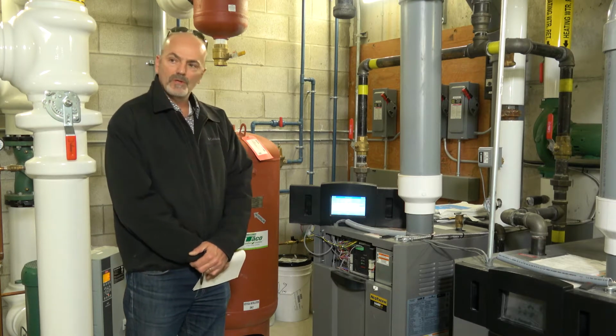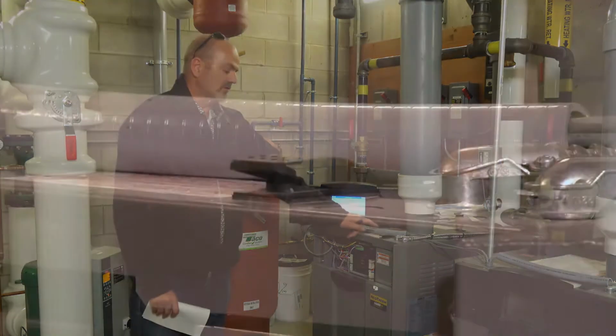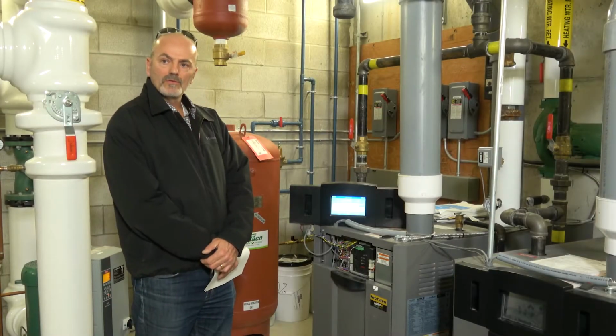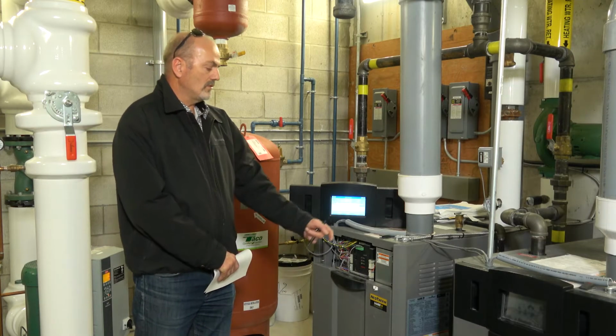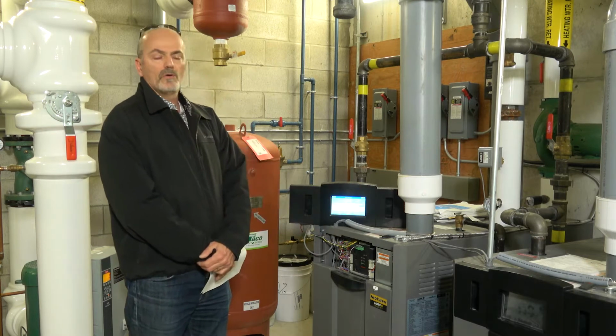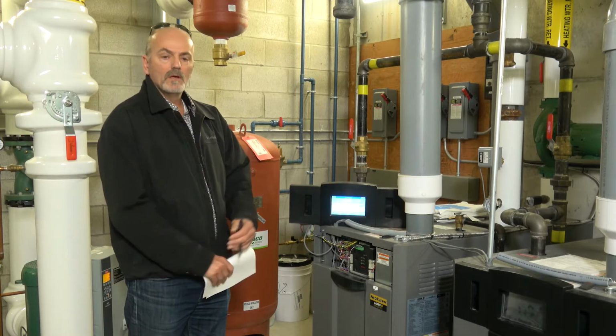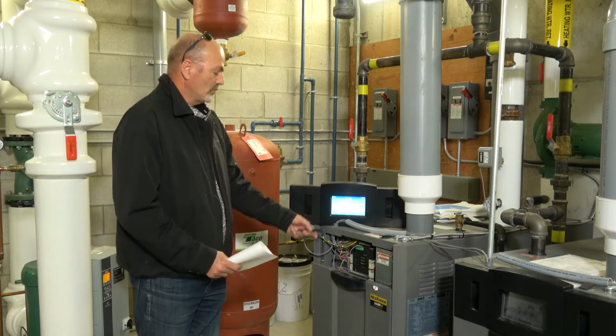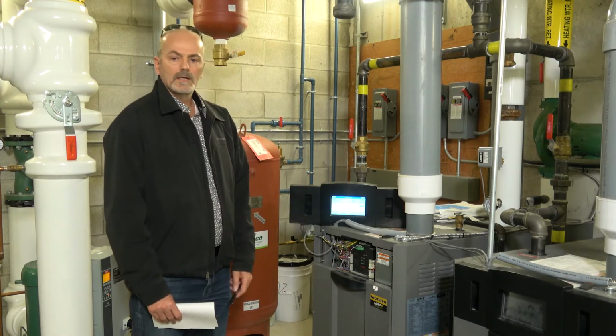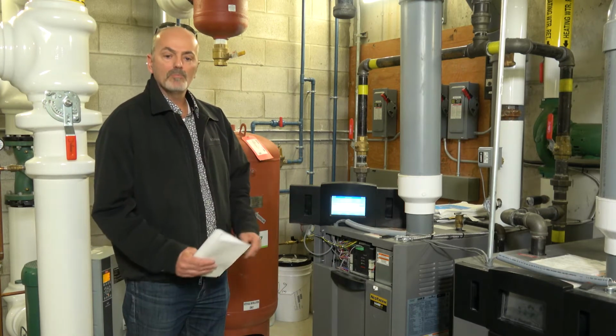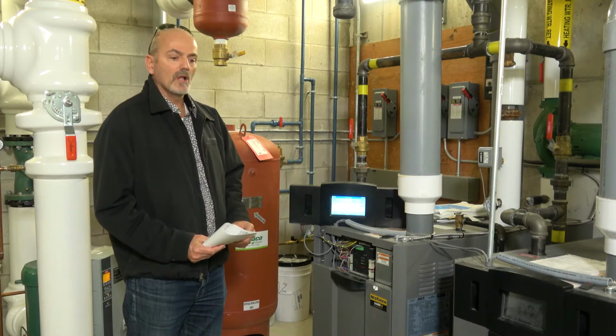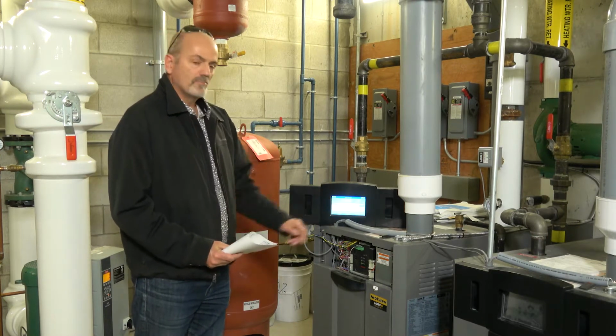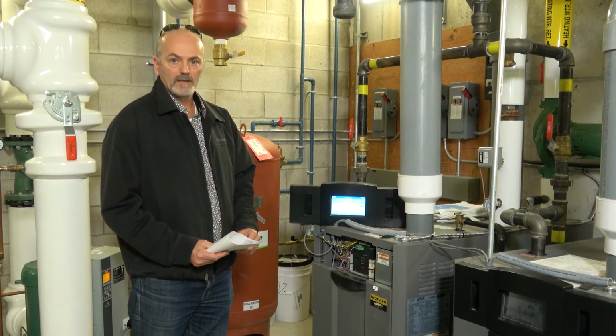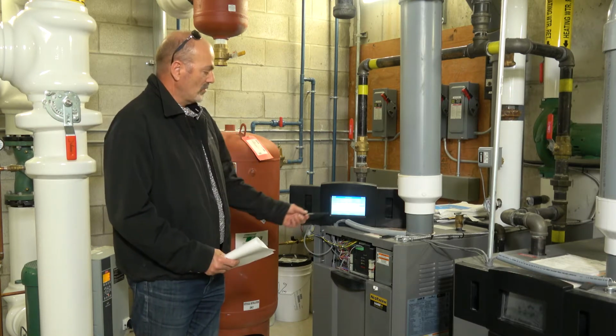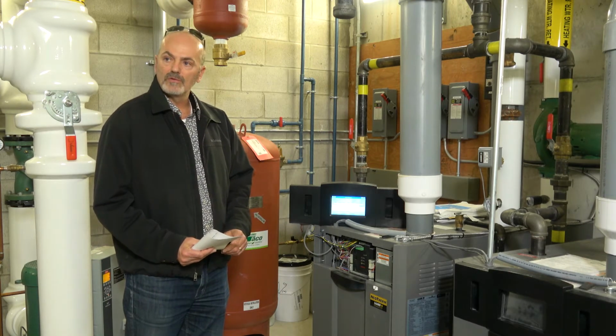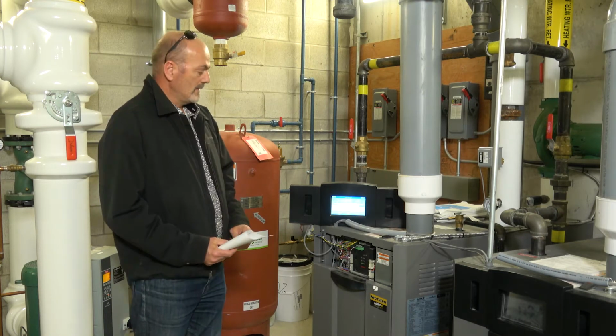If the boiler doesn't reset itself, then you kill the power to the boilers, then press it back on again and allow the boiler to reset and reconfigure. There's an integration period between the control and the master control for that to happen. At that point, it will come back online and you press the blue control button in the center, and it will go back to this home screen, and you'll be able to see it go through its ignition try.